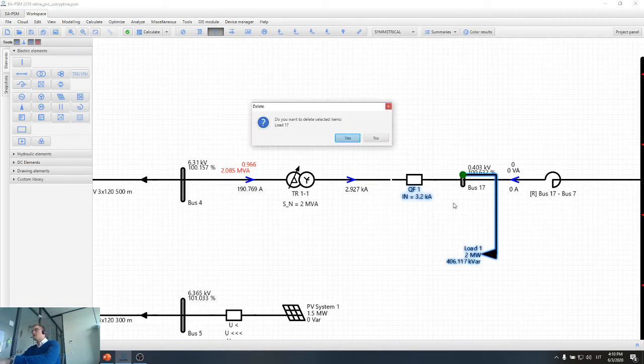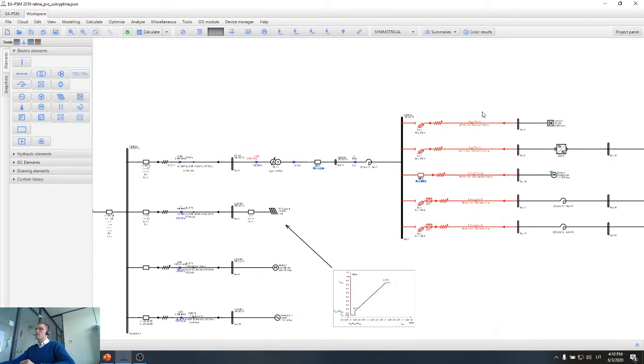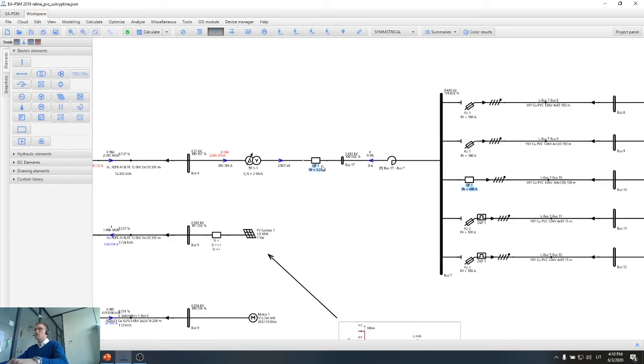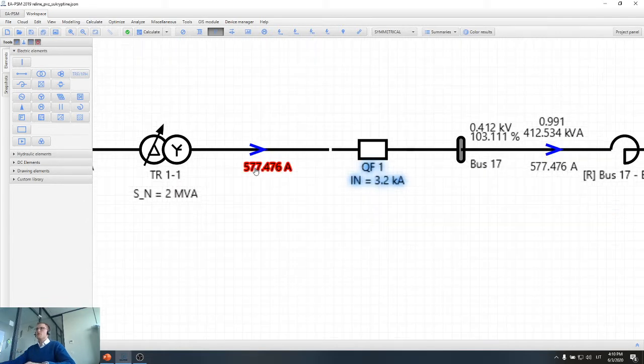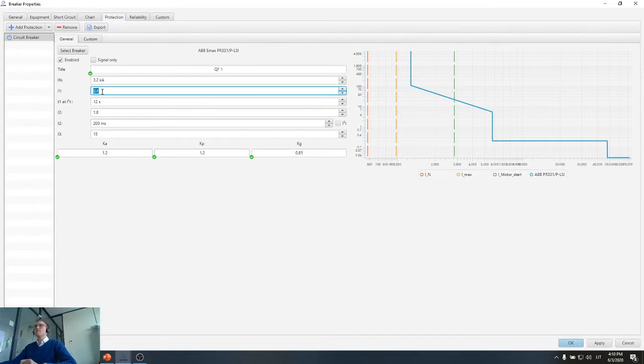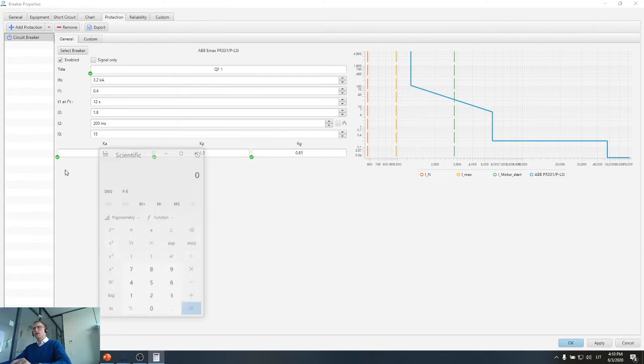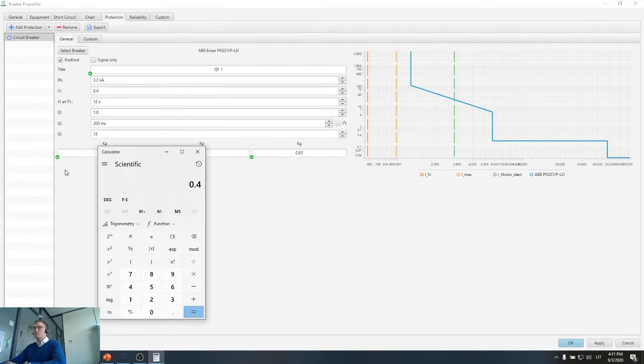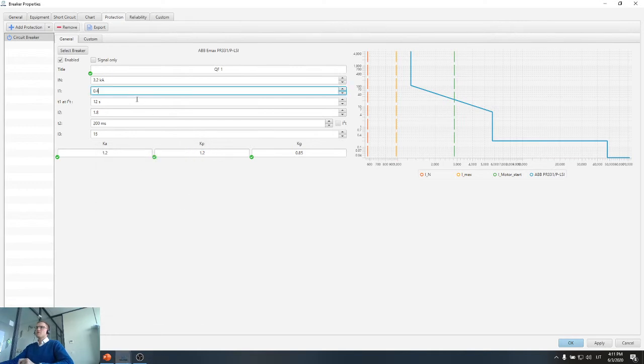Later on, when we have breakers selected according to our transformer, we can select settings for the breaker according to normal current. The normal current is much smaller because now our transformer is not fully loaded, so 577 amps. Therefore, when I open the breaker, I have a current pickup value multiplier set to 0.4. It means the software automatically multiplies 0.4 times 3200, and the pickup value is set to 1280. So these multipliers are used to align the breaker to the actual load, but the nominal rating should be selected according to the transformer power.